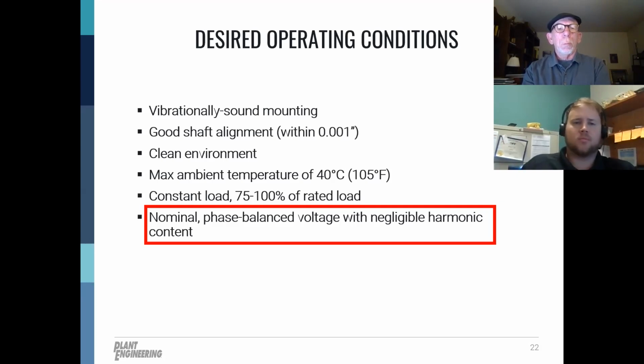The fourth operating parameter we talk about is ambient temperature, and it's very important. The motor nameplate may state a maximum ambient temperature, and if it does, respect that. If you are seeing the ambient temperature consistently above the rating, so if the nameplate says 40 degrees C, but in the heat of summer, maybe in a remote location, you're seeing 45, 50, 60, you might need to derate the motor for that specific application.